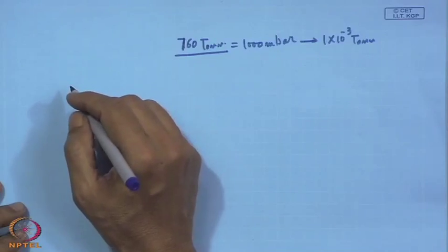Actually, it is the heat loss of a heating element. When the heating element is hot, because of the conductivity of the medium some heat will be taken away. In this case a heating element is put inside the gauge, centrally placed, as we can illustrate here, and when it is hot, the gas molecules can take away the heat just by conduction, and when it heats the wall of the gauge, this heat is transferred to the wall.